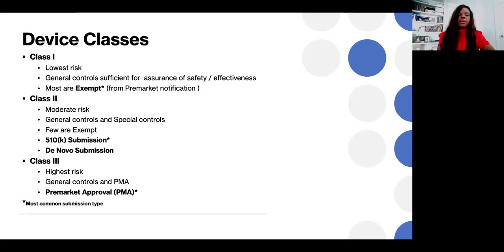new product type. And then the class 3 products, of course, those are the highest risk. These have general controls, but also there are PMA specific controls. And the marketing application is called a pre-market approval application. So here I just put an asterisk for the most common type. In class 1, it would be exempt. Class 2, 510(k), and class 3 would be PMA.